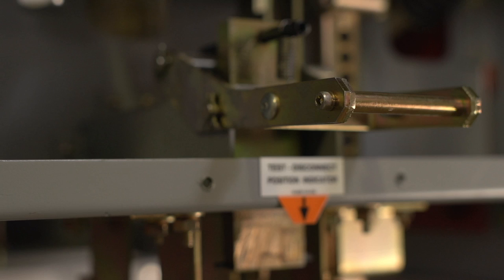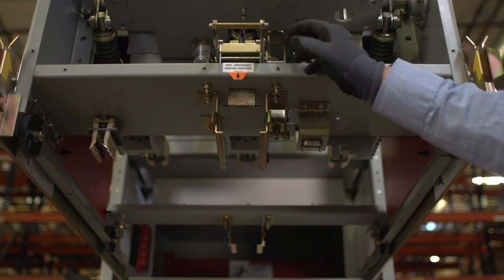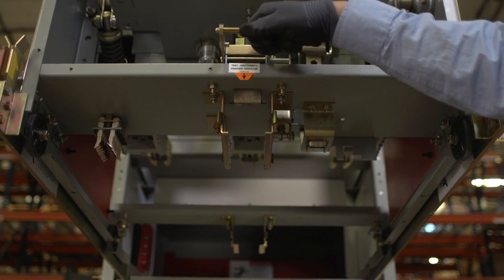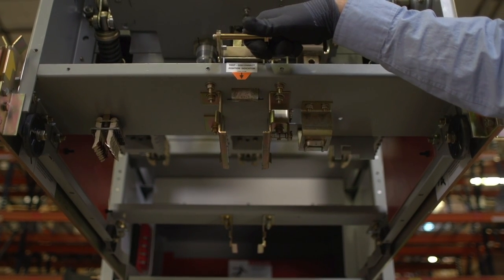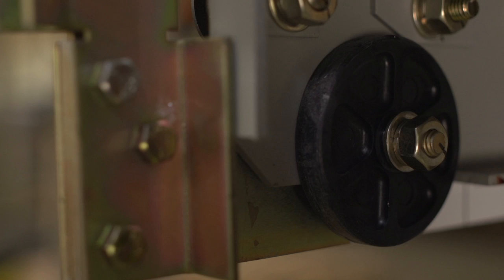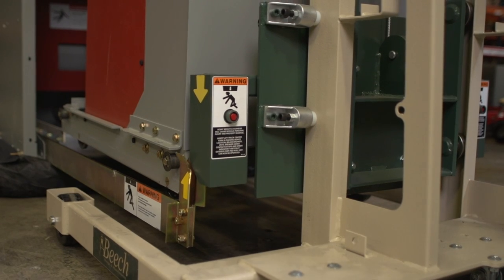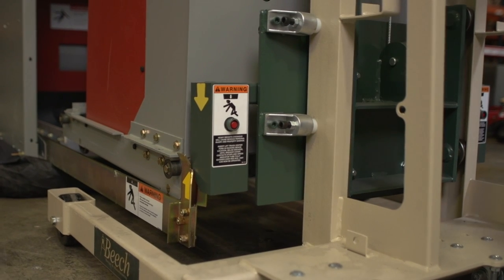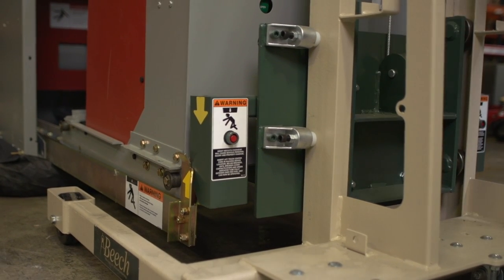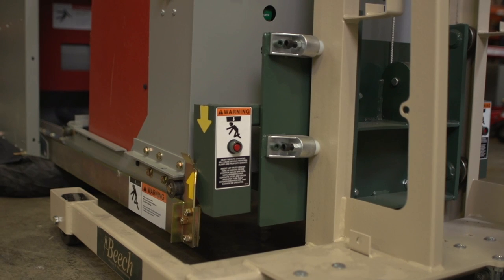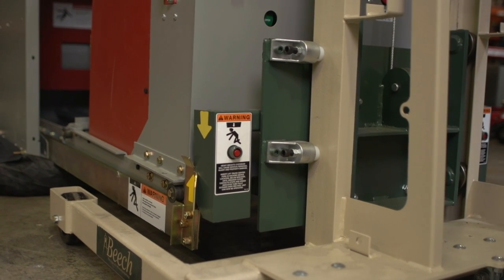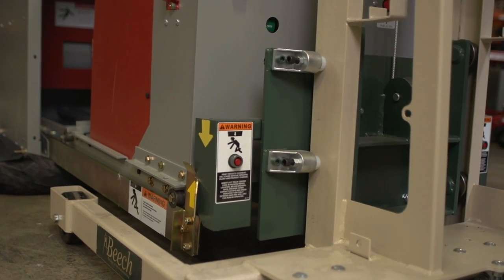The latch mechanism attaches to the drive block, which moves the circuit breaker as you rack it. To remove the circuit breaker, push down the latch release. The circuit breaker moves on the floor on these rugged polycarbonate wheels, secured by steel hardware. Note that there's another set of smaller metal wheels that connect with the rails as the circuit breaker is inserted into the cell.